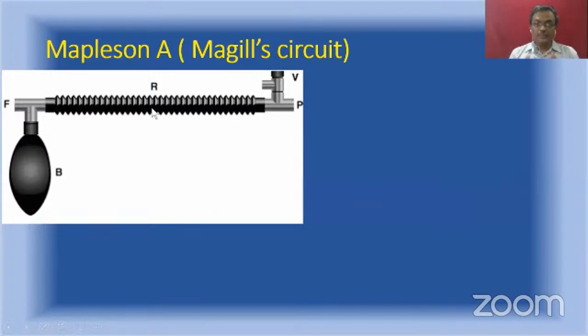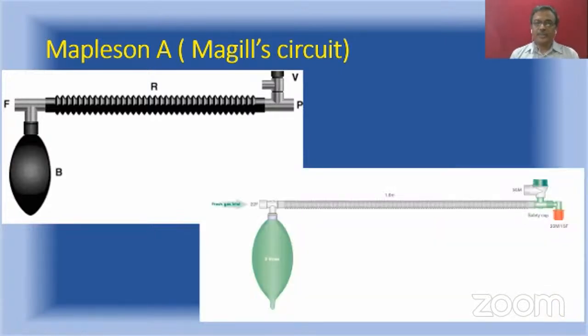So there will be some building up of pressure inside the circuit, which will open up and allow the gas to go out. Now, this is a modified version of the Magill circuit. The difference you see is the scavenging system. See, here there is no scavenging system. Here there is a scavenging system. And moreover, this valve is a metal valve, which is heavy, but this particular valve is made up of plastic. It is not so heavy. And this tube is a little longer. And this is made up of black rubber, but this is made up of plastic.